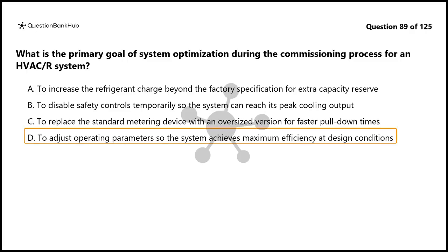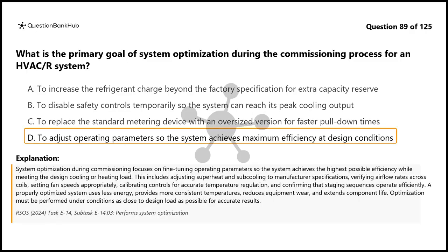The correct answer is D. System optimization during commissioning focuses on fine-tuning operating parameters so the system achieves the highest possible efficiency while meeting the design cooling or heating load.